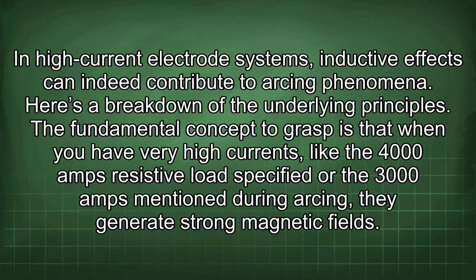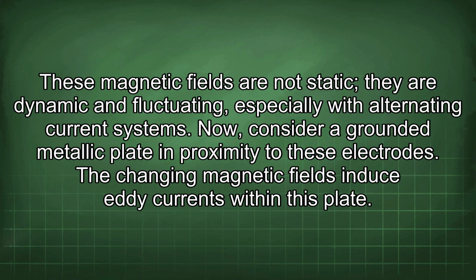High current electrode systems, inductive effects can indeed contribute to arcing phenomena. Here's a breakdown of the underlying principles. The fundamental concept to grasp is that when you have very high currents, like the 4000 amps resistive load specified or the 3000 amps mentioned during arcing, they generate strong magnetic fields. These magnetic fields are not static, they are dynamic and fluctuating, especially with alternating current systems.